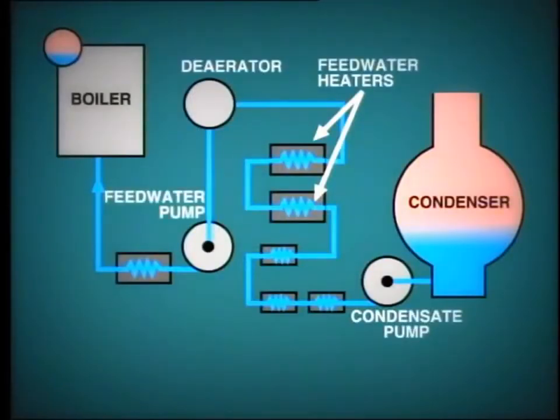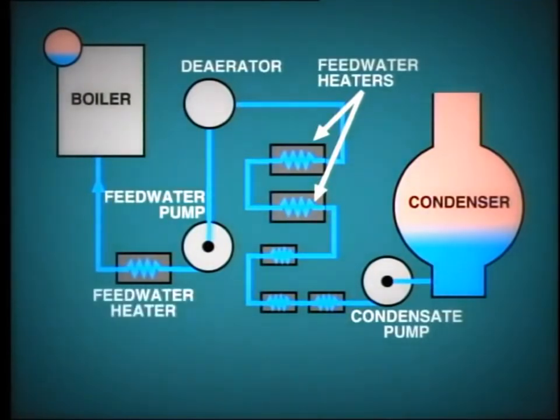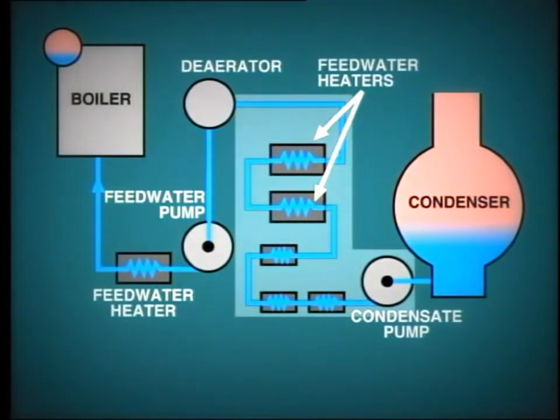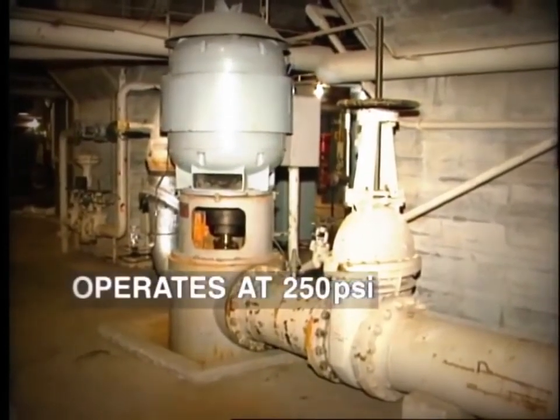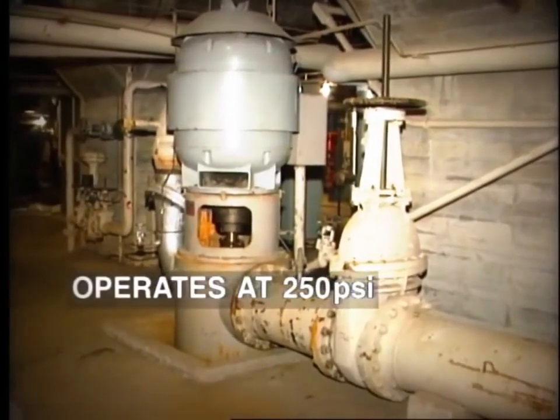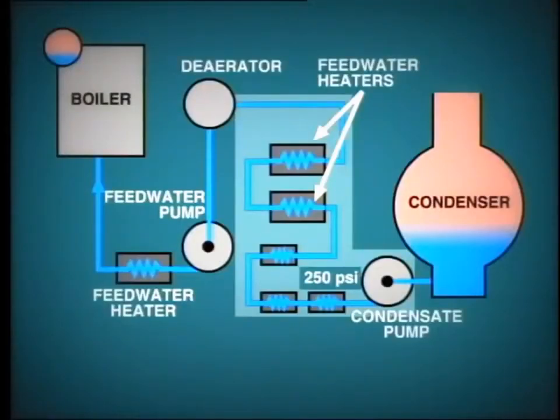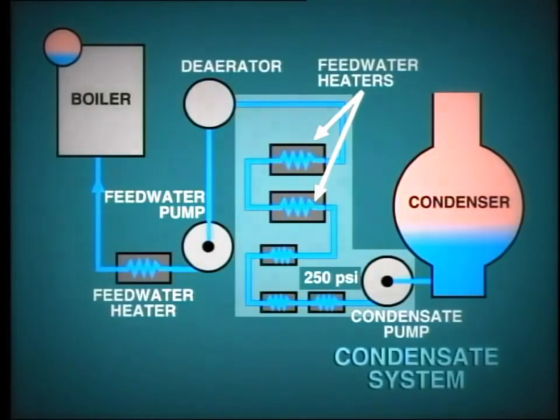The boiler feedwater pump draws condensate from the de-aerator and pumps this through further closed feedwater heaters, one in this example, and on into the boiler. We have, in fact, two pumping loops to transfer the water from the hot well to the boiler. First, the condensate pump pushes the condensate through the coolers and closed feedwater heaters and up into the de-aerator. In order to achieve this, the condensate pump must operate at a pressure of about 250 PSI. This part of the system is known as the condensate system.